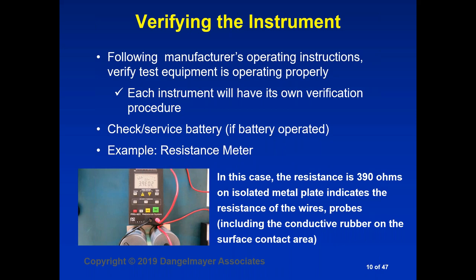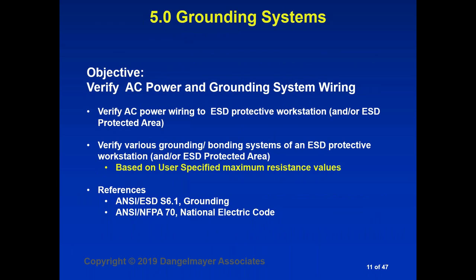Now, when it comes to verifying your instruments, each one of them will have some sort of verification procedure. You may need some kind of test facility supplied by the manufacturer to verify the instrument. But this should be the first step in the process to make sure that your instruments are okay. The picture you see here is of a resistance meter, and the manufacturer says that if you put both of the probes on a metal plate so that they're essentially connected together, you should read about 390 ohms in this particular case. So you'd know when you put those probes on that metal plate and measure the resistance, if you came into the 390 ohm range, you'd know that you were making accurate measurements with your meter. So once you've verified your instruments, you're ready to go out into the work area where you're going to try and do a compliance verification.